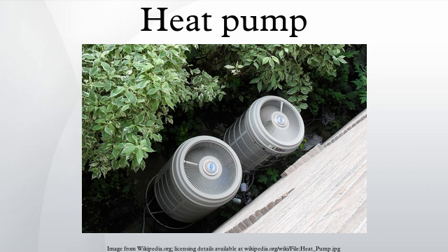Ground source heat pumps, also called geothermal heat pumps, typically have higher efficiencies than air source heat pumps. This is because they draw heat from the ground or groundwater, which is at a relatively constant temperature all year round below a depth of about 30 feet. This means that the temperature differential is lower, leading to higher efficiency. Well-maintained ground source heat pumps typically have COPs of 4.0 at the beginning of the heating season, with lower seasonal COPs of around 3.0 as heat is drawn from the ground.